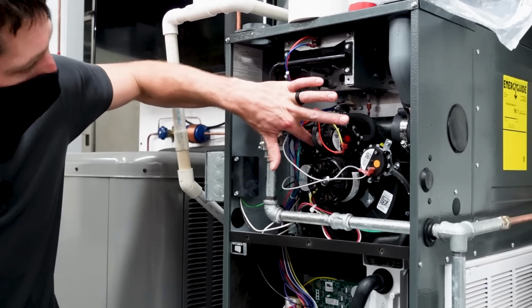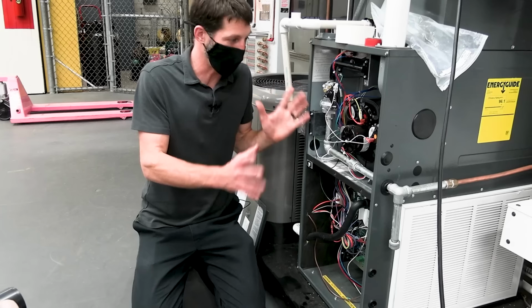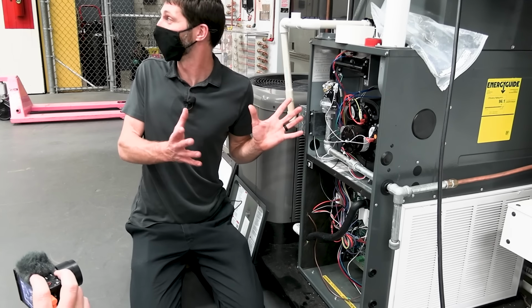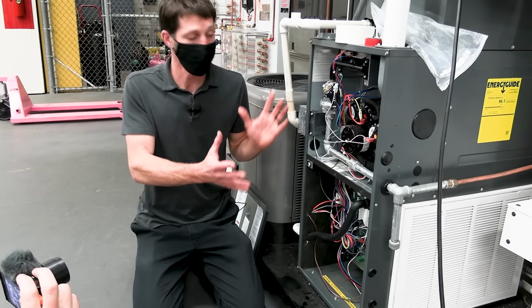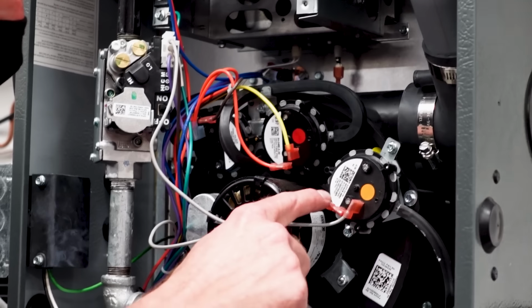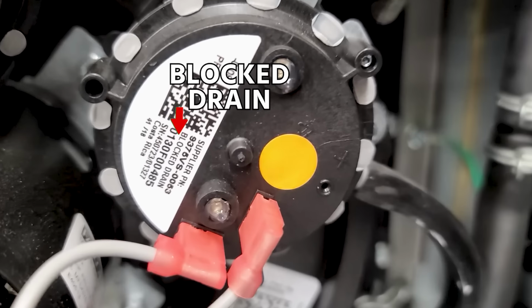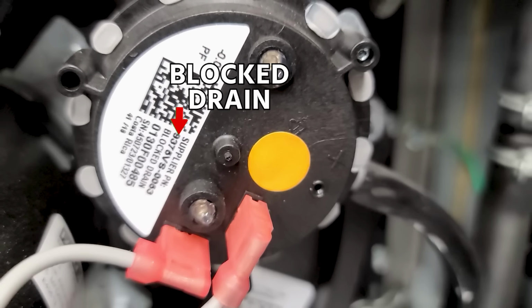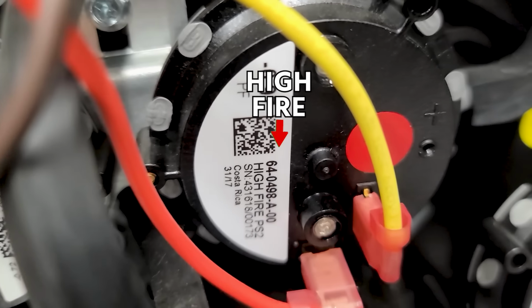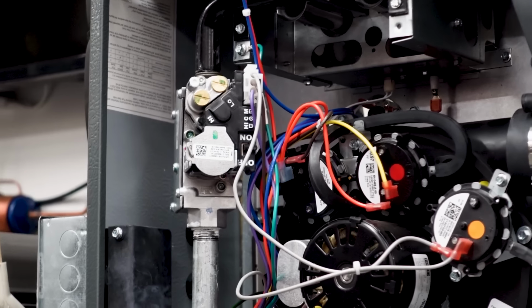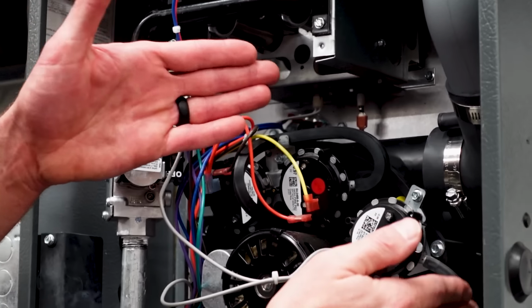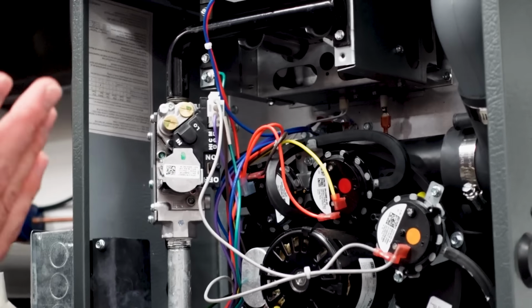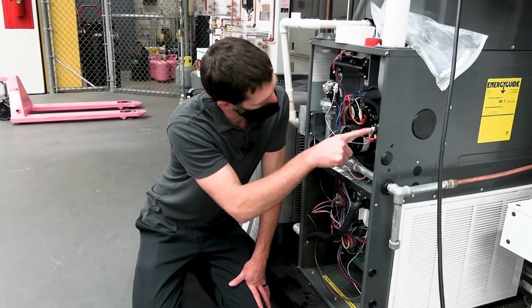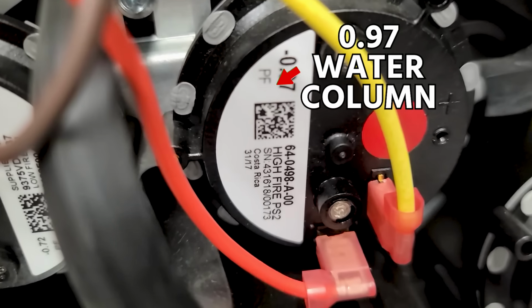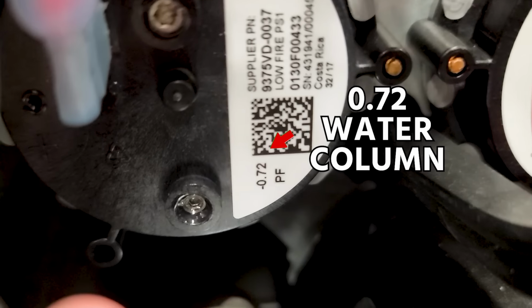You have 3 pressure switches right here. And this, I was telling Brian, is a real nice furnace to learn on, even though it's a high efficiency one. The reason for that is right here, it says block drain on this pressure switch. Awesome. This one says high fire, and this one says low fire. They normally never say that, so you have to look at where the tubing is going in order to determine that as well. These have the inch water column measurements like 0.97 and 0.72.